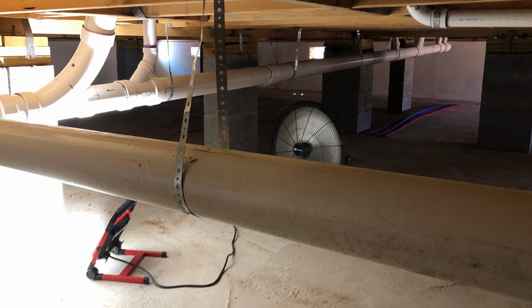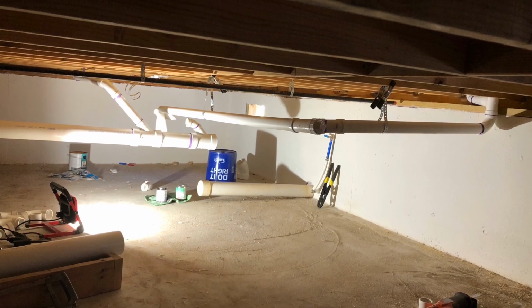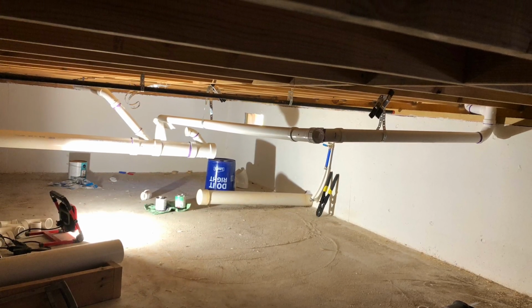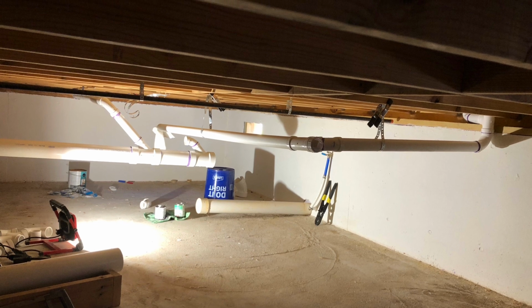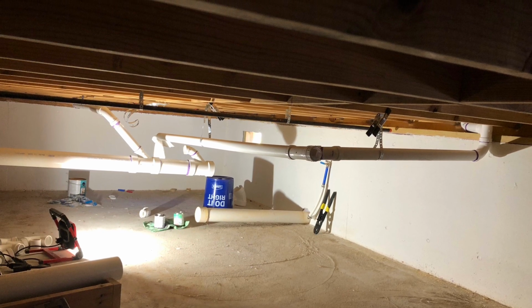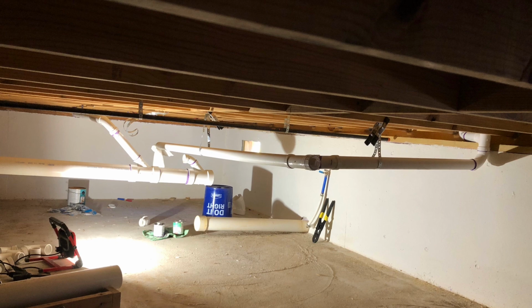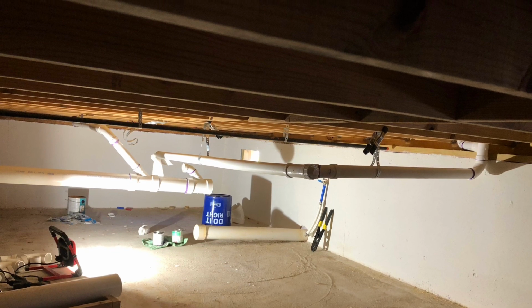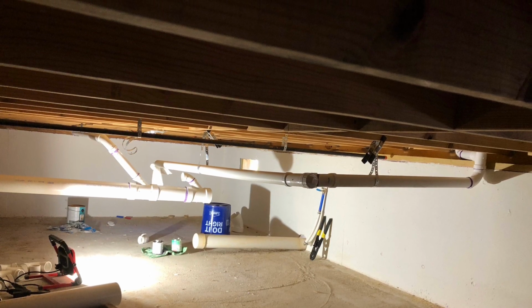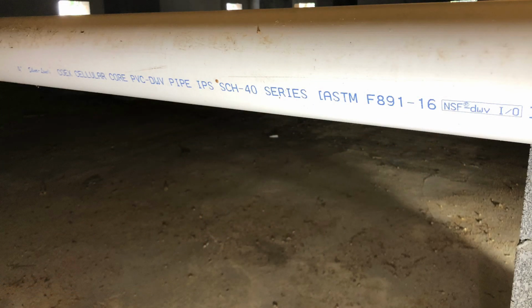I did go over a lot on sizing and oversized my drain lines. You can see the smallest diameter pipe in the crawl space is 2-inch, leading into the top portion of the 4-inch, where the drain water comes into the top portion of the pipe versus the side. Here you can see the pipe that I used, DWV pipe, Schedule 40, standard piping for drain systems, and in this application it worked just fine.